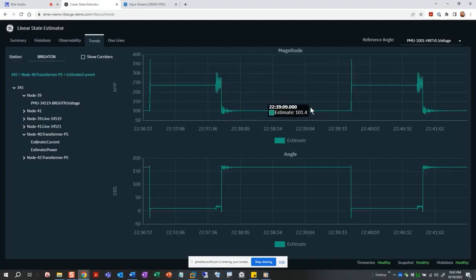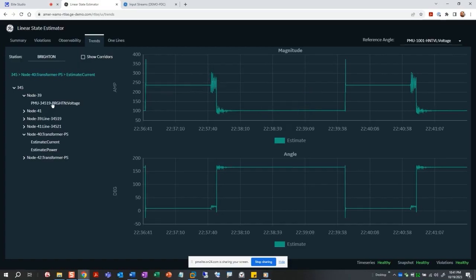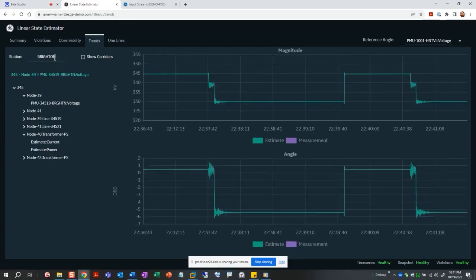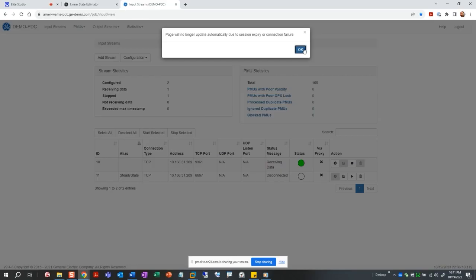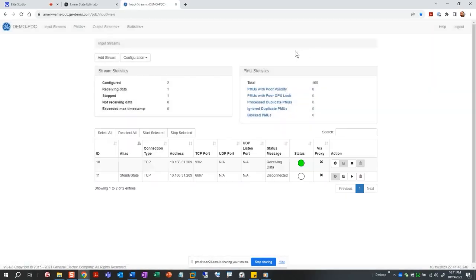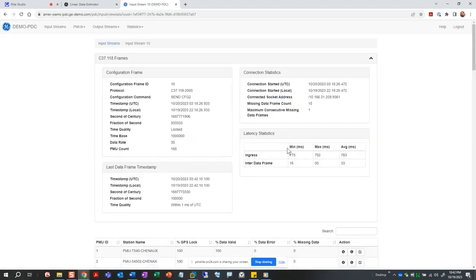Again, trending the different, I believe are from the islanding conditions that are routinely going on. And one other thing that I mentioned, like Manu had mentioned, this is a state estimator. So it's capturing the state of the grid, but it's also doing estimation. So it's basically cleaning up the data and making corrections. So if there's any kind of incoming incorrect data, it's going to correct for that and solve to an appropriate solution. So I just wanted to take an example here.